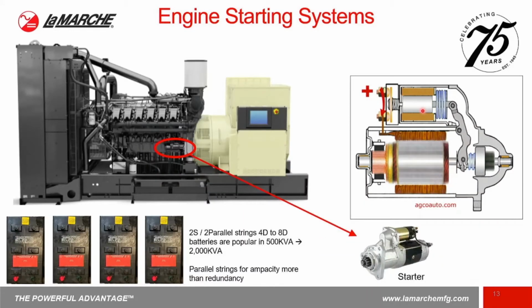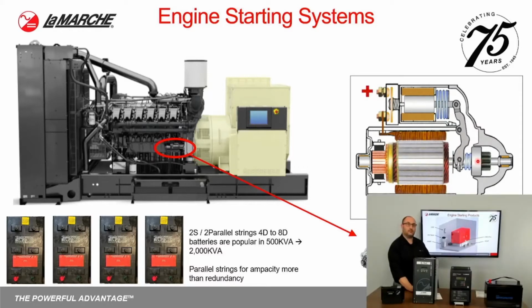So looking closer at the engine starting system and focusing on the starter, you can kind of see from the graphic over here, as the solenoid up on top is being energized, it closes the contacts over here, which allows current to flow to the winding on the motor. So also you notice this cantilever lever. As the contactor pulls in, it is drawing the motor such that the pinion can engage the flywheel, and that's what actually spins the engine over in order to build compression in order to get the engine started. This is no different than the starter inside your average automobile. It's only bigger.